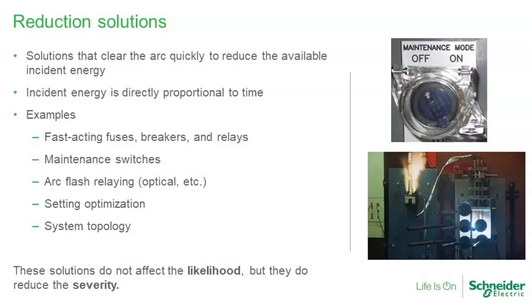And as we talked earlier, incident energy is proportional to time. You clear the fault more quickly through using things like fast-acting fuses, circuit breakers, or relays. We can reduce those energy levels. Sometimes we can't do that without messing up the selective coordination that we like to have in a system. So we do things like put maintenance switches on the breakers or relays so that we only have to have this coordination for a short period of time. You turn the maintenance switch on, settings are reduced, worker is protected. When the work is done, you turn the maintenance mode back to off. So you kind of restore normal selective coordination. Energy level goes up, but you're not as concerned at that point because there's no one there actively working on the system anymore.